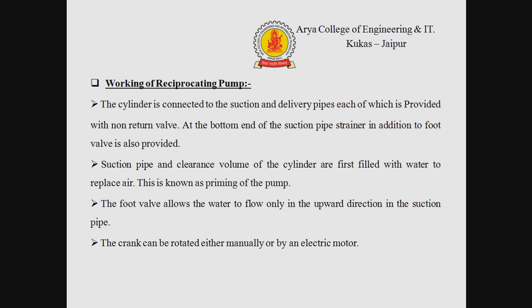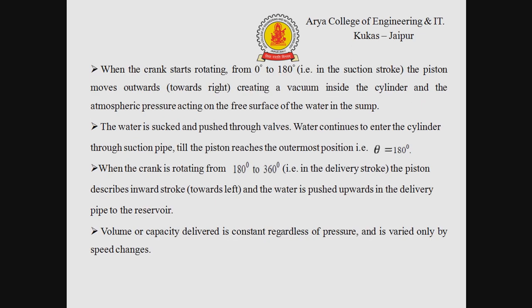Now we discuss about the working of the reciprocating pump. The cylinder is connected to the suction and delivery pipe, each of which is provided with a non-return valve. At the bottom end of the suction pipe, a strainer and foot valve are also provided. The suction pipe and clearance volume of the cylinder are first filled with water to replace air — this is known as priming of the pump. The foot valve allows water to flow only in the upward direction. The crank can be rotated either manually or by an electric motor.